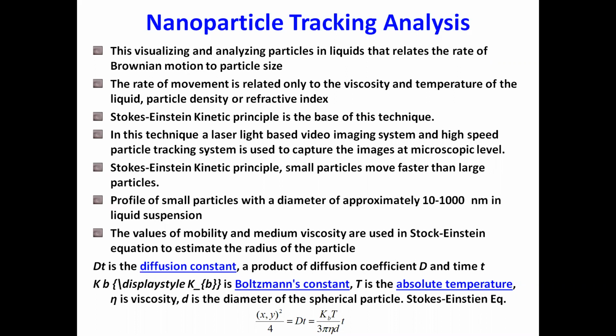The rate of movement is related only to the viscosity and temperature of the liquid, because as you enhance the temperature, viscosity will reduce. As you play with the viscosity, the Brownian motion will also be affected. But the particle density and refractive index of that liquid will not influence the size. So the Stokes-Einstein kinetic principle is the base for this technique. The Stokes-Einstein equation is written here.